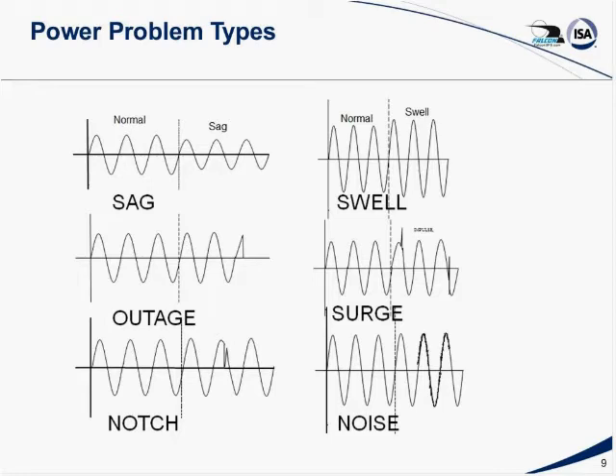A notch is a switching or other disturbance off your normal power voltage. It lasts less than half a cycle, but the polarity initially is always opposite of the polarity of the normal waveform. And then we have our infamous noise riding on the signals, which is either capacitively or magnetically coupled into our circuitry, becoming conducted noise.